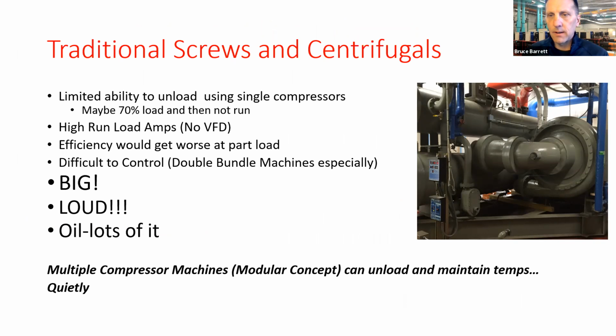I mentioned screws or centrifugals. They make double bundle heat recovery chillers still to this day. They're very large. They typically do not have VFDs, so you don't get that low inrush benefit. As they unload, they typically get worse in kW per ton. They demand large flow rates, larger minimum flow rates than modular machines. They're big. They can be very loud and a lot of vibration. The picture I show up on top was in one of the buildings next to the Capitol in Wichita. 16-inch base, steel bases, spring isolators, and every time it turned over, they'd have to pay peak rates with those large compressors. Also, it's lots and lots of oil to maintain that system, which degrades over time.